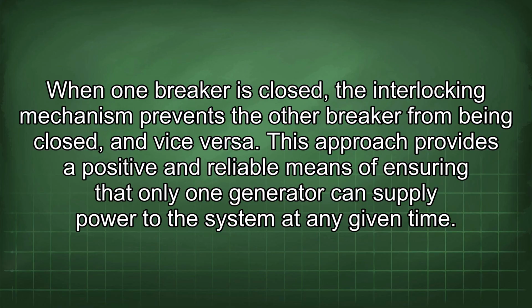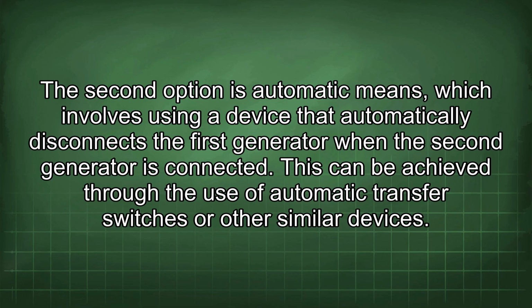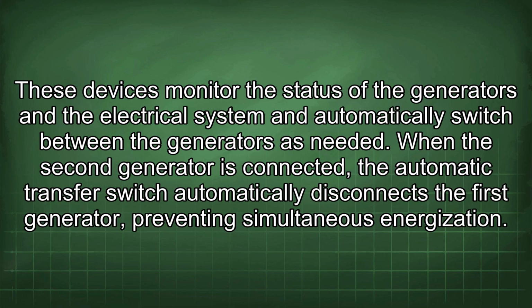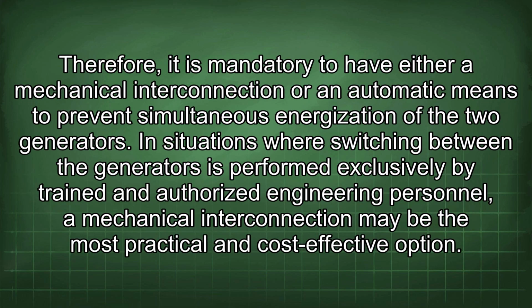at any given time. The second option is automatic means, which involves using a device that automatically disconnects the first generator when the second generator is connected. This can be achieved through the use of automatic transfer switches or other similar devices. These devices monitor the status of the generators and the electrical system and automatically switch between the generators as needed. When the second generator is connected, the automatic transfer switch automatically disconnects the first generator, preventing simultaneous energization.